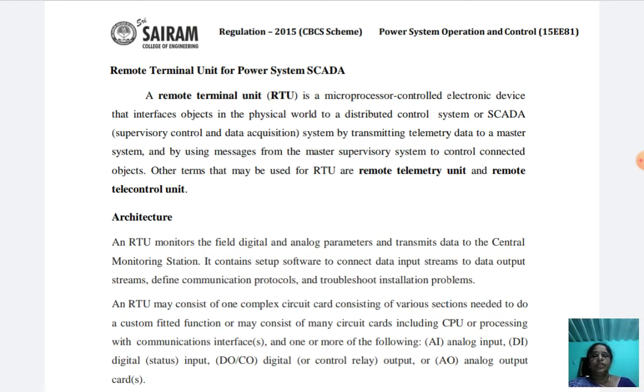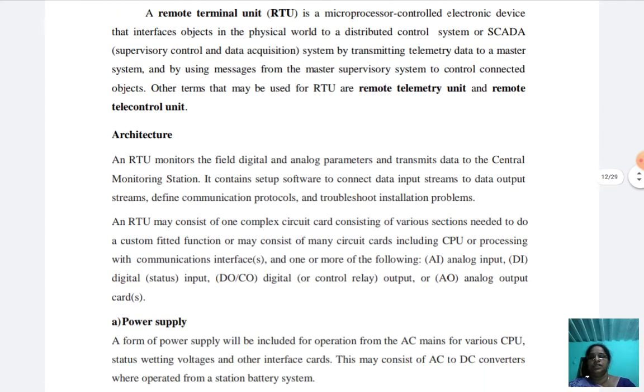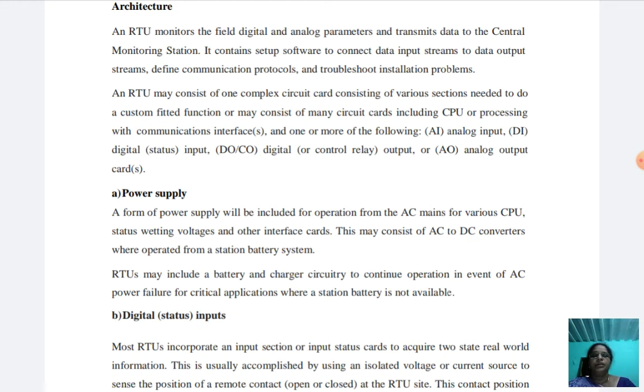The remote terminal unit consists of one complex circuit card with various sections for a custom-fitted function, or may consist of many circuit cards including a CPU or processing unit with a communications interface and one or more of the following: analog input, digital input, digital output, control relay output, or analog output cards. The power supply is included for operation from the AC mains for various CPU, status wetting voltages, and other interface cards. The power supply mainly consists of AC to DC converters operated from a station battery system.